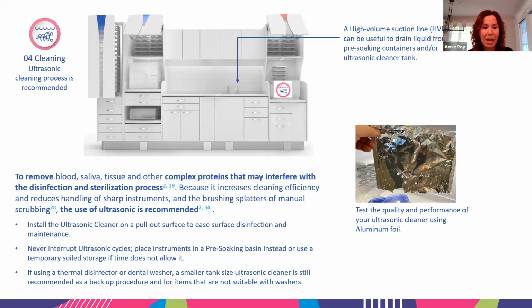if time does not allow for the ultrasonic cleaner at that time. If you're using a thermal disinfector or a dental washer, then a smaller tank size ultrasonic cleaner is still recommended as a backup procedure for the items that are not suitable for the washer. And test the quality and performance of your ultrasonic cleaner using aluminum foil.